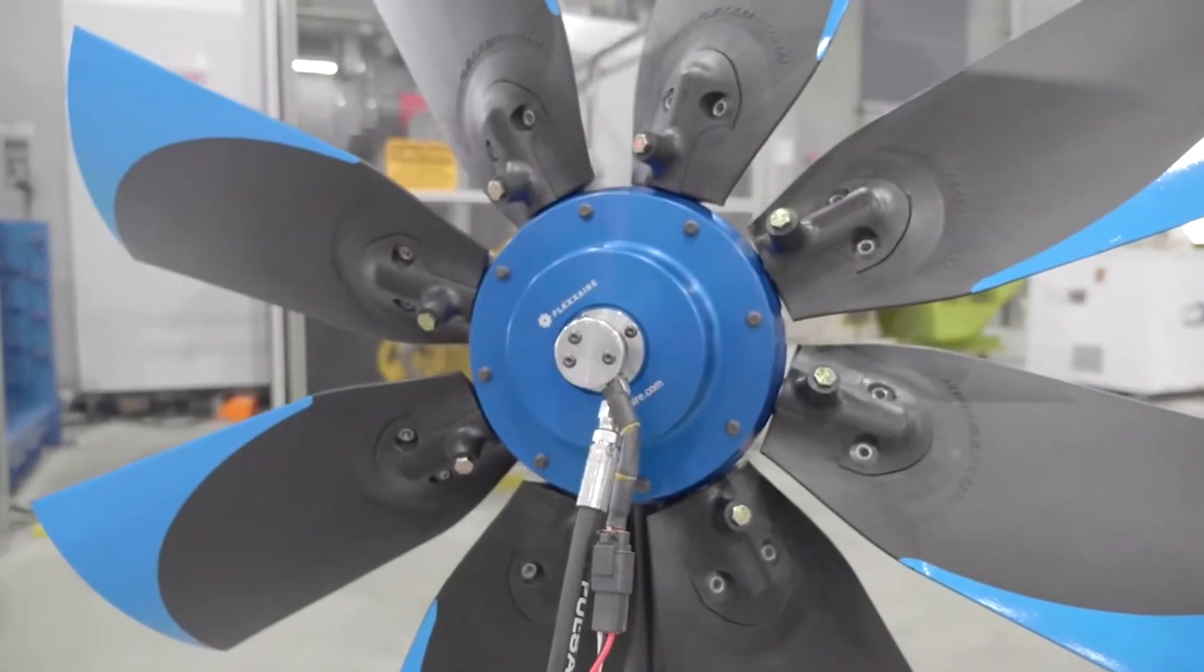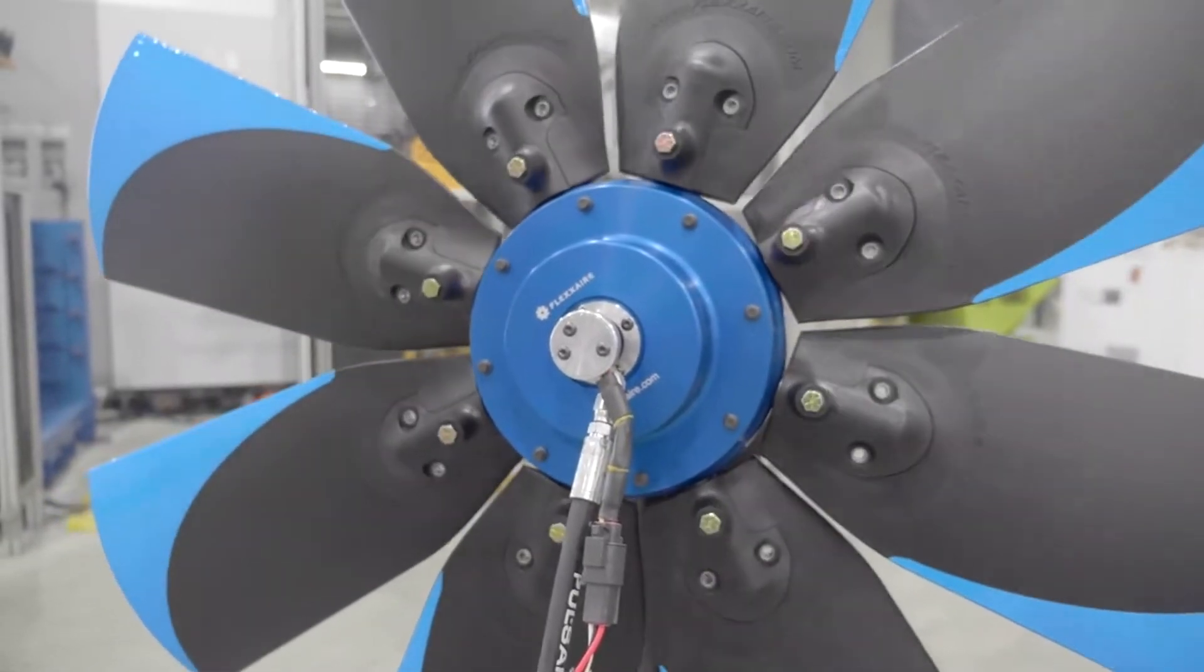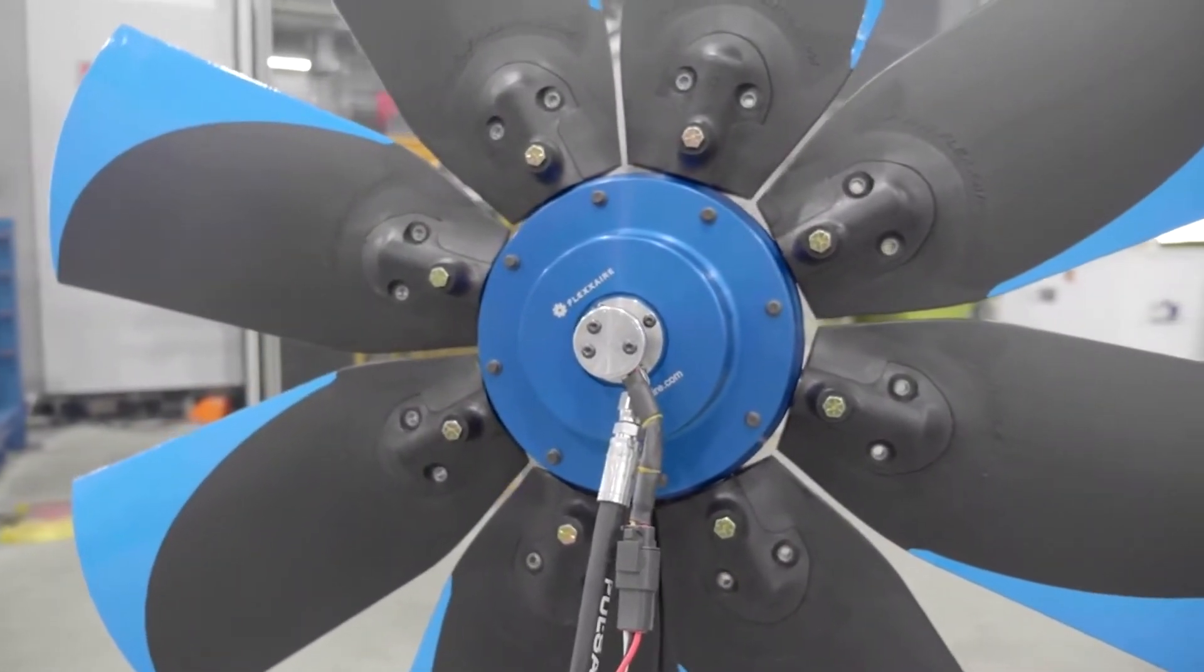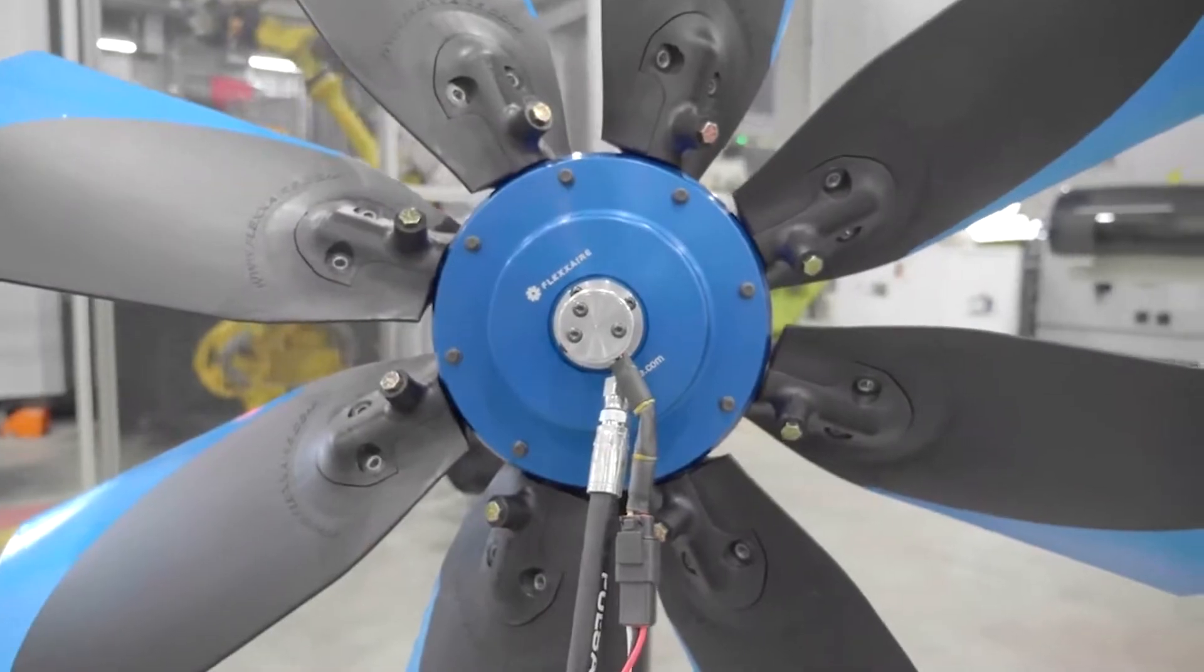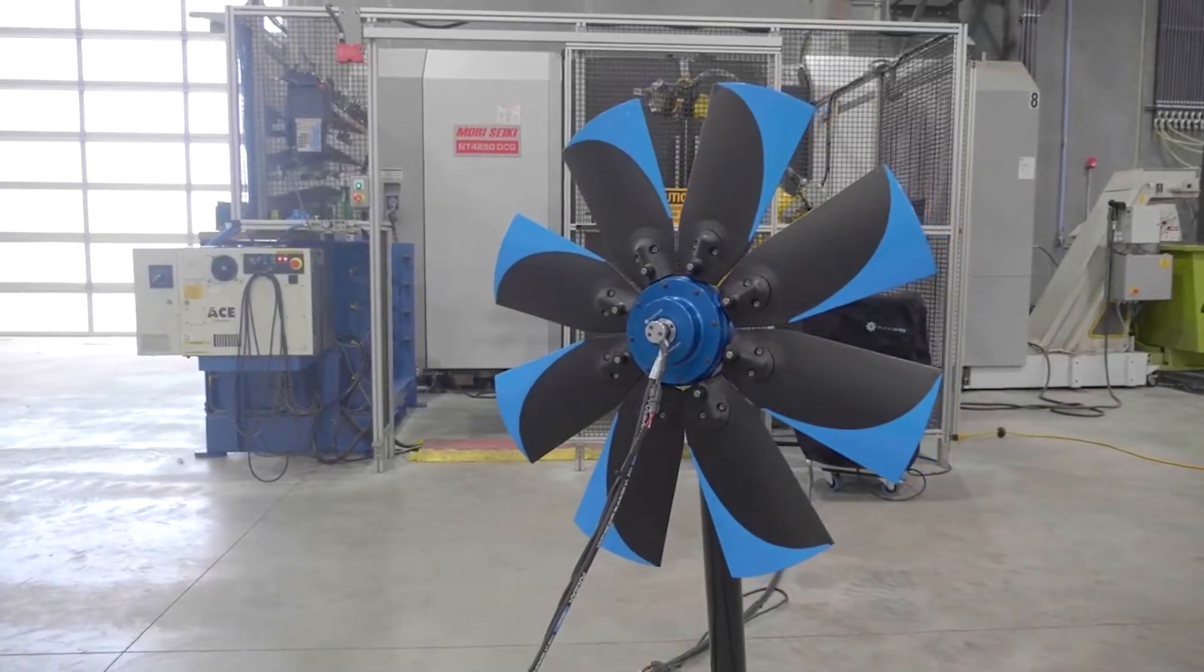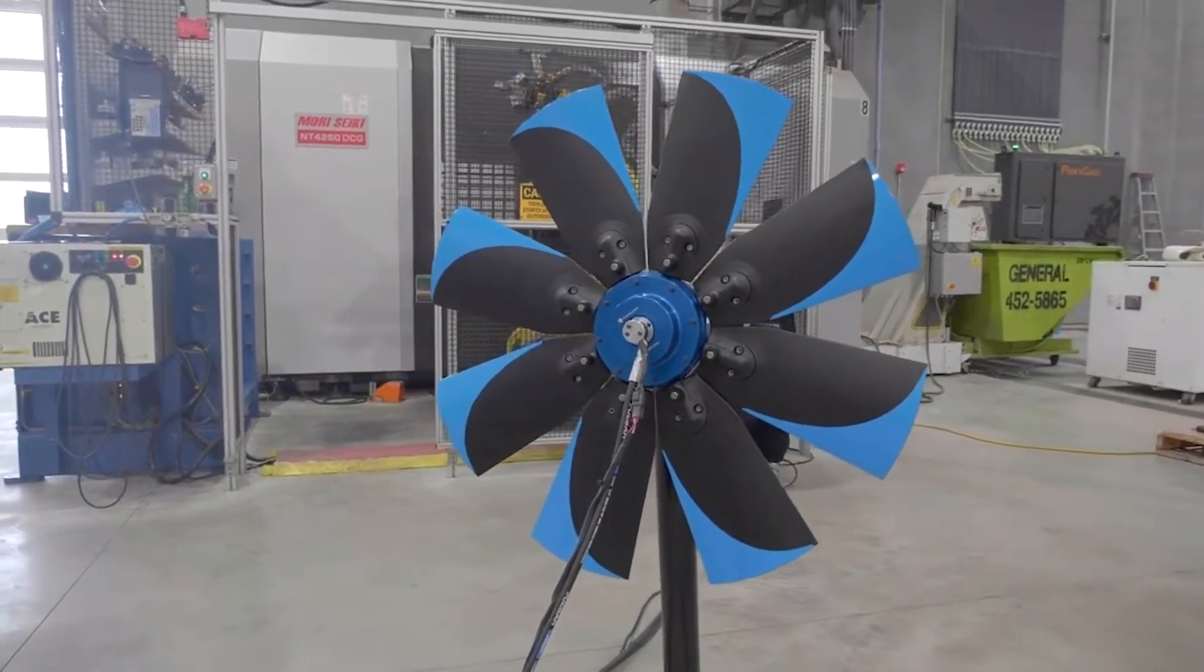As we reverse the pitch, the width of the blade envelope is reduced, meaning the widest the fan will be is in the full pitch position. During reverse and neutral cycles, there is a reduction in horsepower draw and sound level.